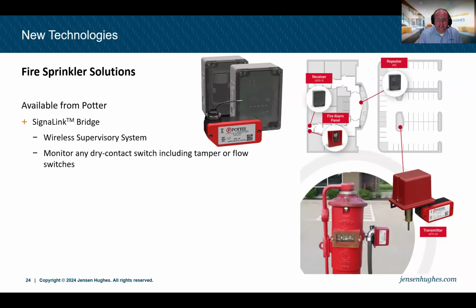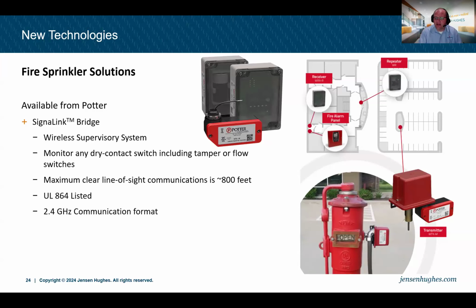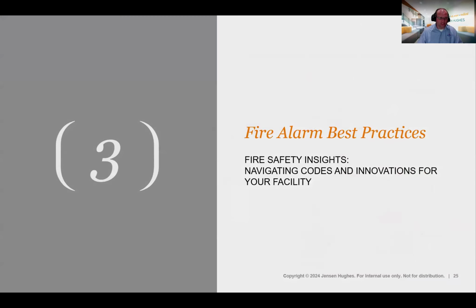Well, now there's a wireless option here, a wireless supervisory system. We can monitor any dry contact whatsoever, including tamper, flow switches, and PIV valves through this bridge. It has a clear line of sight of about 800 feet, so that'll go quite a ways. It is UL 864 listed, and it's using a wireless format in the 2.4 gigahertz range. And the nice thing, it's compatible with any fire alarm system. So even if we have a wired route today, maybe that wired route becomes compromised by water, we need to replace that. Well, we can do that, and it can be a very, very effective way to fix older systems.